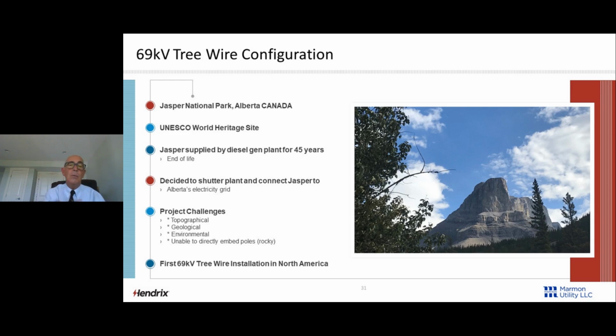Up until 5, 6, 7 years ago, we had only built 69 kV in spacer cable. We have a project in Jasper National Park, which is in Alberta, Canada. It's a UNESCO World Heritage Site. It's a very special place for our planet. That city in the middle of that national park was supplied by a diesel gen plant for 45 years. It reached the end of its useful service life. They wanted to refurbish that diesel plant. The Public Utility Commission said no go, it's not going to happen. You've got to connect Jasper to Alberta's electricity grid.